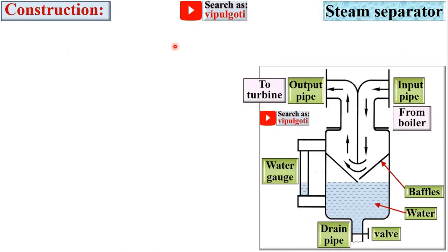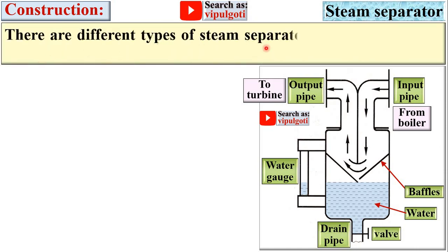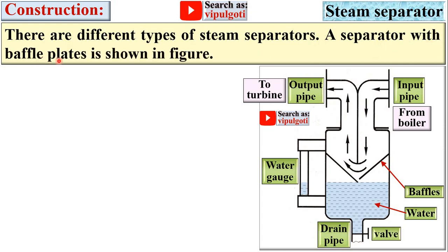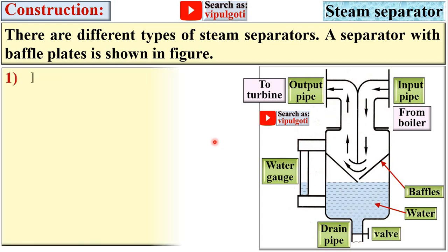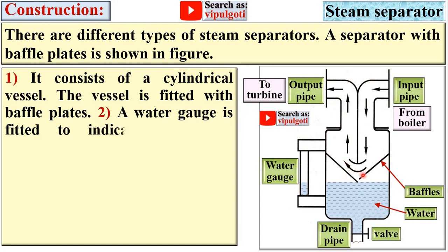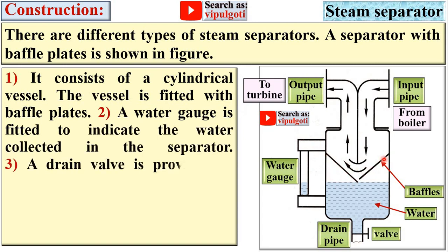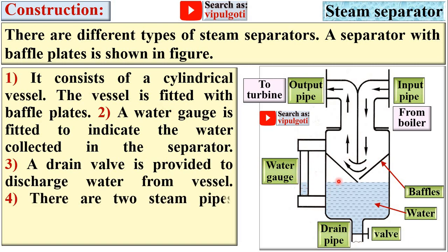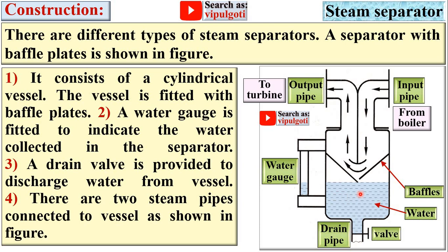Now the construction of the steam separator. There are different types of steam separators. A separator with baffle plates is shown in this figure — this is called the baffle type steam separator. It consists of a cylindrical vessel fitted with baffle plates. A water gauge is fitted to indicate the water collected in the separator. A drain valve is provided to discharge water from the vessel. There are two steam pipes, both connected to the vessel as shown in the figure.